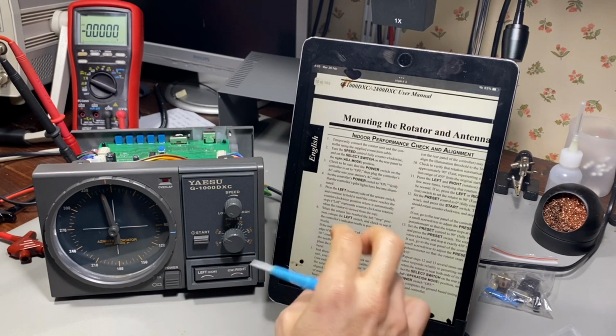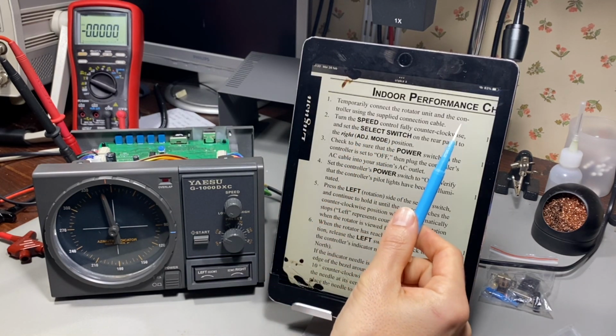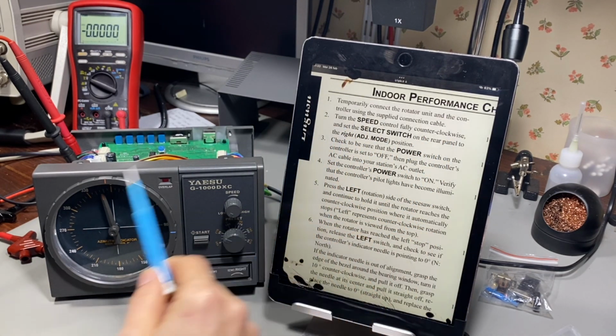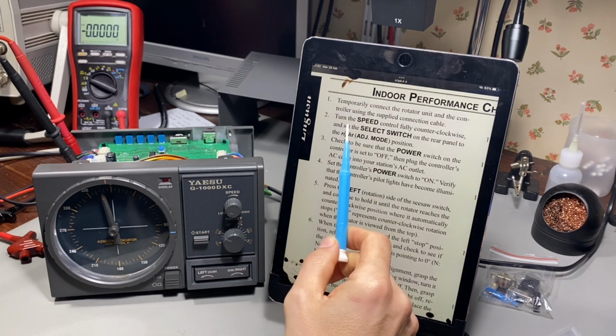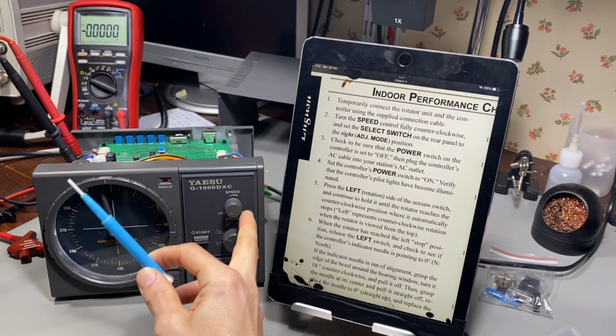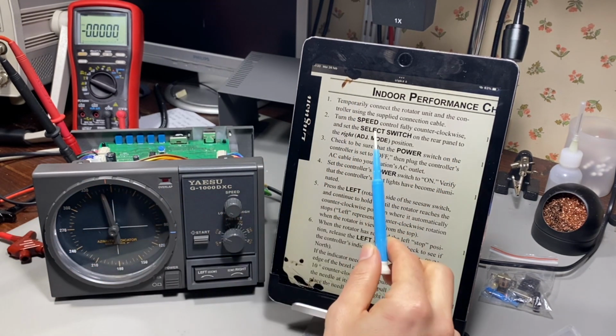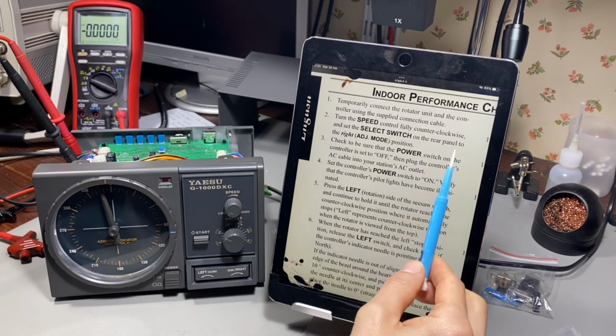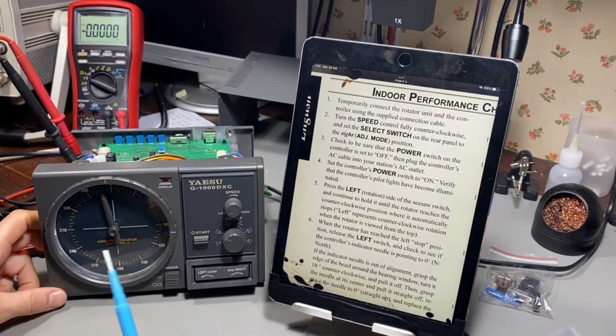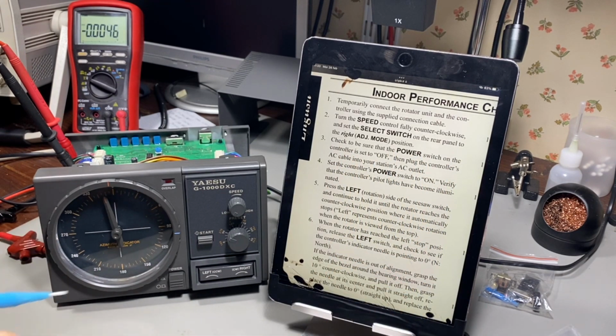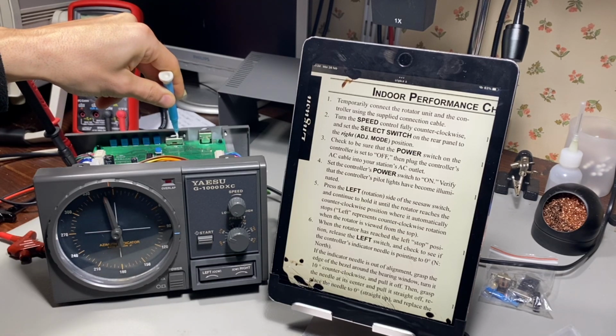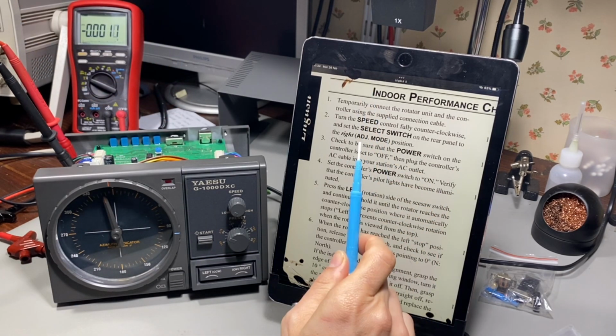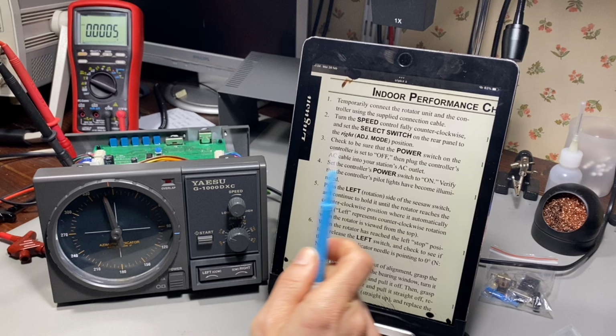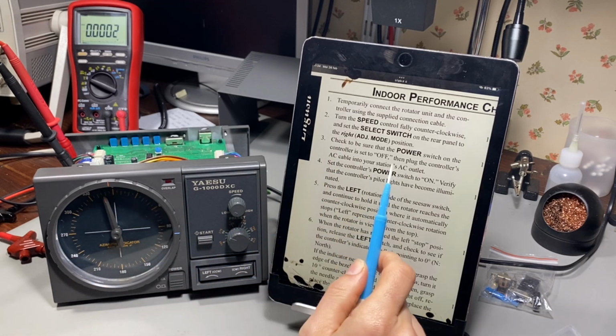Indoor performance check: temporarily connect the rotor unit as I said. Turn the speed control fully counterclockwise to low, and select the switch on the rear panel to the adjustment position. The switch is this one here, flipped like that. Check to be sure the power switch on the controller is set to off, then plug it into the mains.